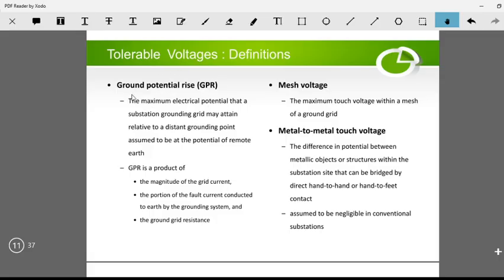The first parameter is called the ground potential rise, or GPR. This is the maximum electrical potential that a substation grounding grid may attain relative to a distant grounding point, assumed to be at the potential of remote earth.